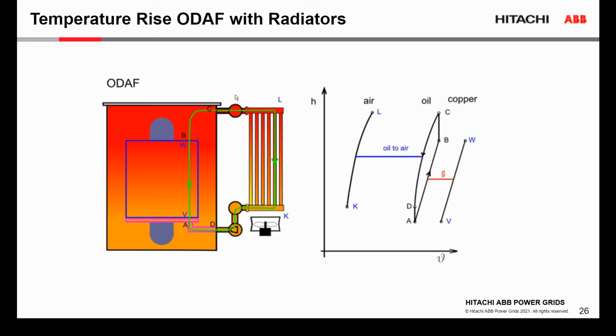ODAF cooling we can use in the transformers with radiators and pumps as well. So in this case, oil from the radiators is pumped into the chamber located under the windings, and it is pushed to the windings. And as you can see, the top oil temperature, or the temperature rise at the top and the bottom of the tank, is very similar. The difference is only 5-8 degrees. But at the same time, by going with the directed oil flow into the windings, we can reduce significantly the gradient from the windings to the oil.